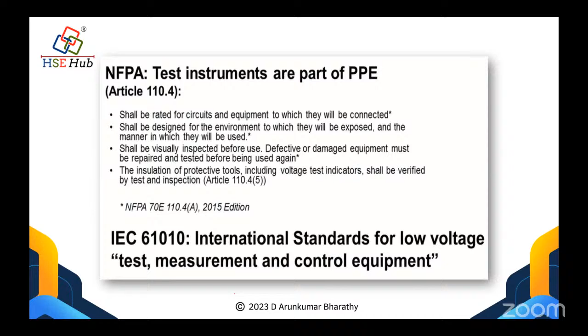The fifth mistake is misidentification of circuits and voltage levels. Maybe an experienced person knows this, but sometimes this also happens. So it is mistaking neutral or ground, like red and black, leading to electrocution, right? Not properly verifying the absence of voltage before touching the component, right? Because sometimes some components may have a fault current maybe, right? So we have to verify properly. Then measuring a circuit without confirming the voltage rating. In fact, this point will come repeatedly, because when a test and measuring equipment fails and causes risk for the user is when the range is exceeded or out of range.